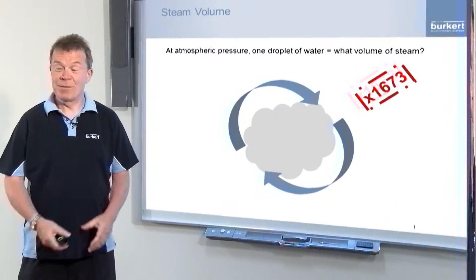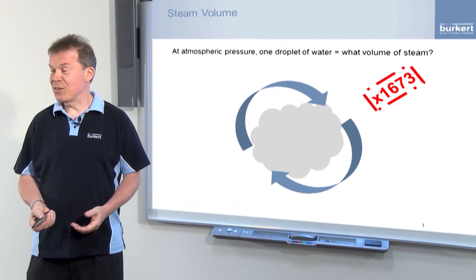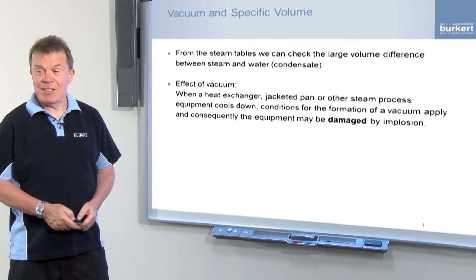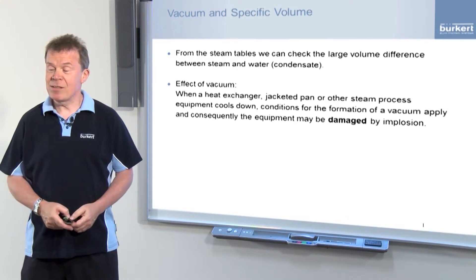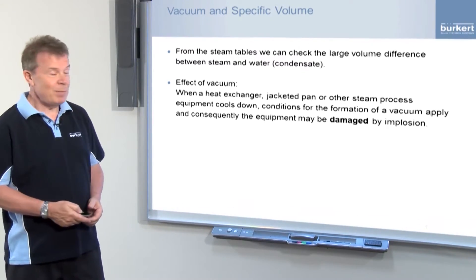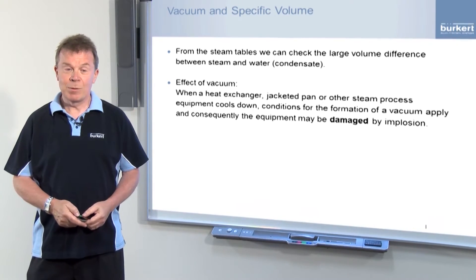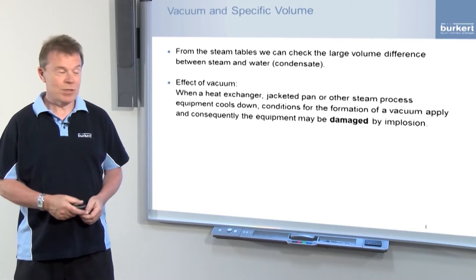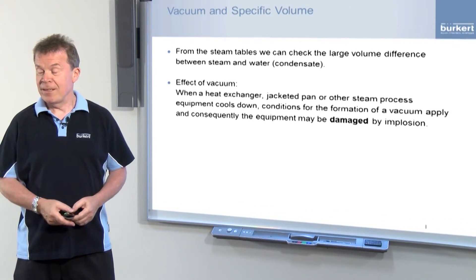It's important: if you mishandle steam, not only can it be inefficient, it can also be dangerous. We want to send you away after the day with a better appreciation of how you can improve things in terms of efficient use of steam, but also with a very good eye on the safety of steam. From the steam tables we can see that one droplet of water when converted to steam increases in volume by 1,673 times. When steam condenses it also reduces in volume by 1,673 times, and that reduction in volume can cause the creation of a vacuum. When a steam process such as a heat exchanger or a jacketed pan cools down, the conditions apply for the formation of a vacuum, and this vacuum can cause the equipment to be damaged by implosion.